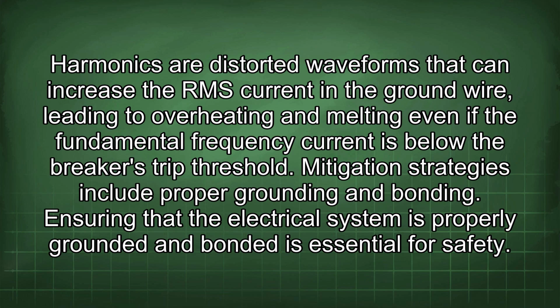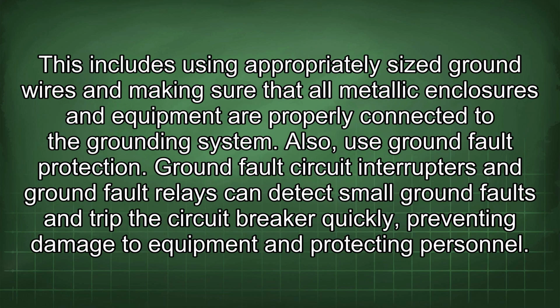Mitigation strategies include proper grounding and bonding. Ensuring that the electrical system is properly grounded and bonded is essential for safety. This includes using appropriately sized ground wires and making sure that all metallic enclosures and equipment are properly connected to the grounding system. Also, use ground fault protection.